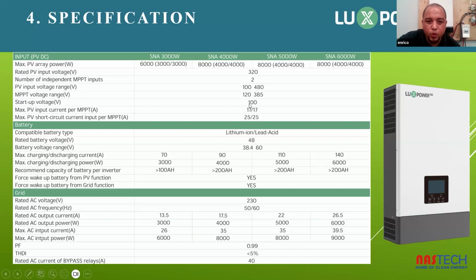So it's important also to make sure that you design the PV or the solar panel array according to the startup voltage of the inverter, because some of the panels have about 32 volts, and when you have about 3 panels at 33 volts or 32 volts, you're 3 or 5 volts short of the 100, and the inverter will see the voltage on the MPPT, but will not be able to use it until it reaches the startup voltage of 100. The max solar panel PV input current will be 17. At the moment, it's 13. The max PV short circuit current input per MPPT is 25. The SNA is compatible with lithium ion and lead acid.